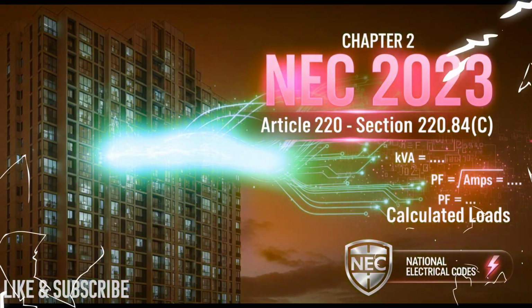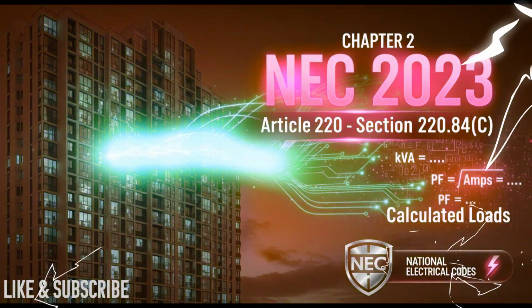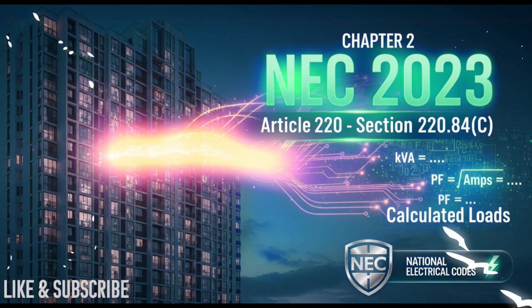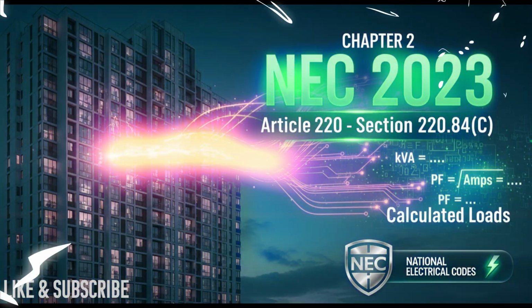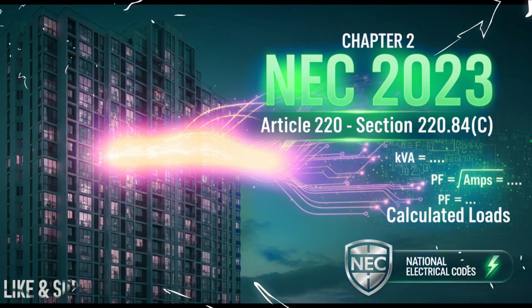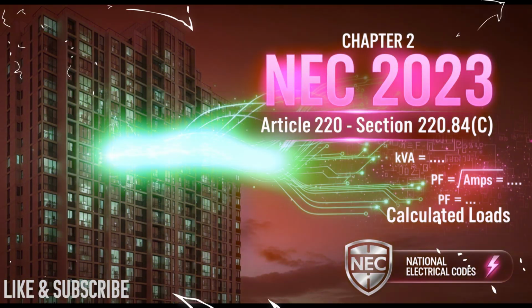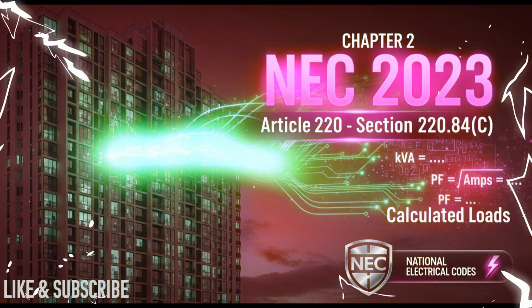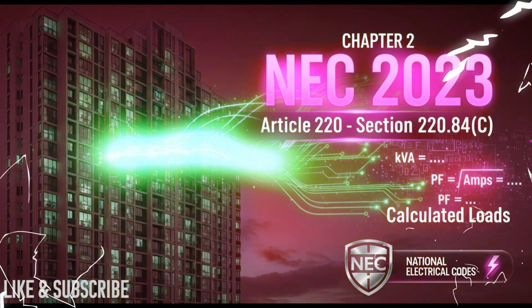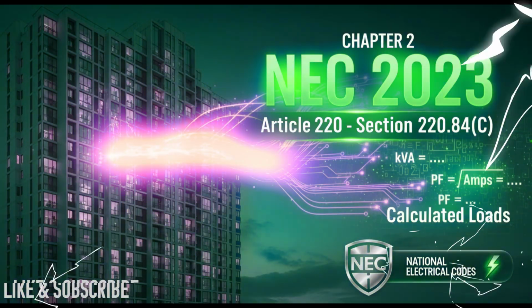Wow. Okay, so let's try to connect this back to the bigger picture then. It's a really clear illustration of how the code drives not just safety, but design and cost too. You've got these 5 mandatory steps. Yep, 5 distinct inputs. Starting with that conservative 3 VA per square foot for the general ambient power. Right, the baseline. Then adding fixed 1,500 VA chunks for those dedicated kitchen and laundry service. Mandatory additions. Then meticulously documenting the nameplate ratings of all the specific big fixed appliances. Using the manufacturer's number. Accounting for every single permanent motor, even the ones outside the units. Can't forget those. And finally, making that smart choice between the heating load and the cooling load, taking only the bigger one. That's the whole process in a nutshell.